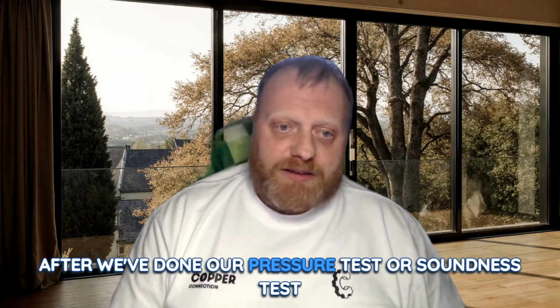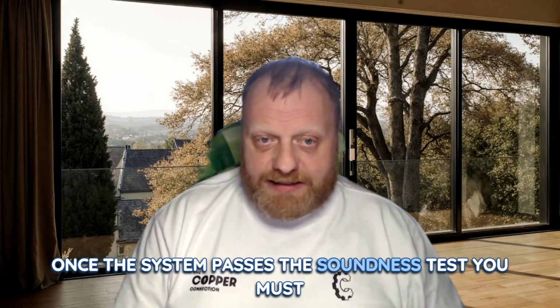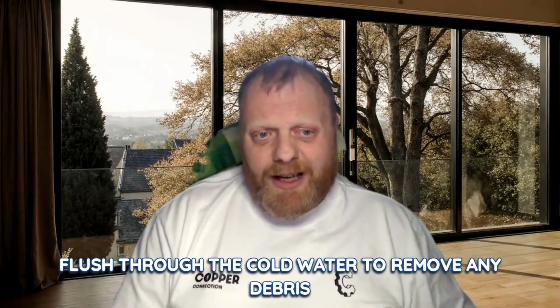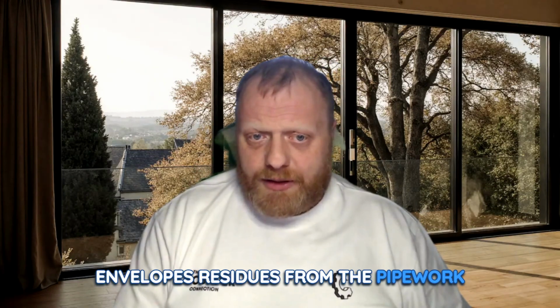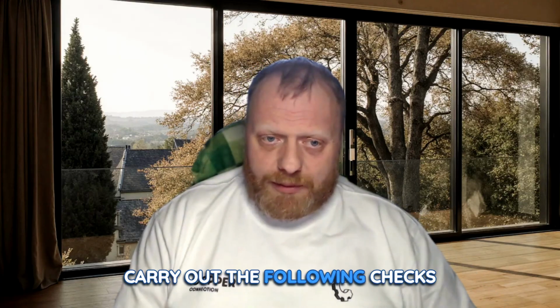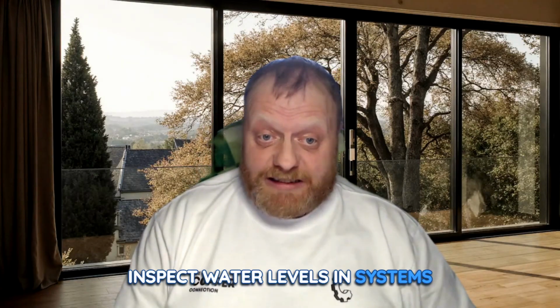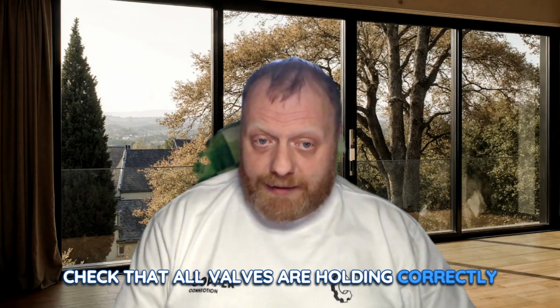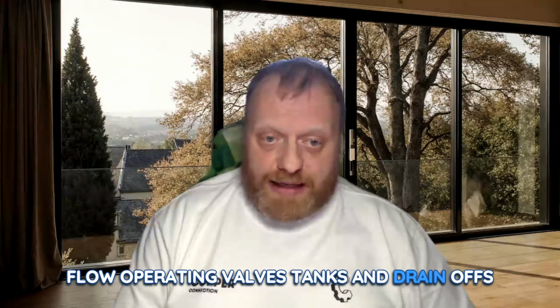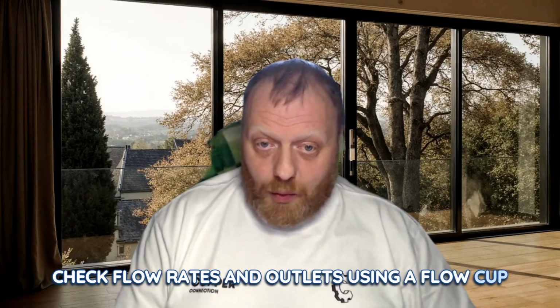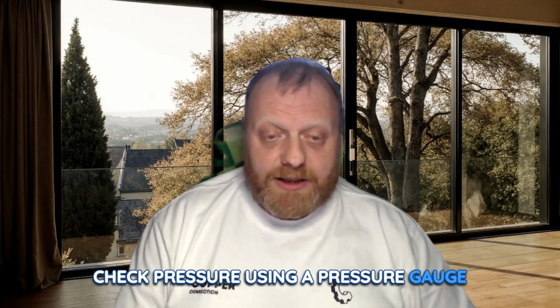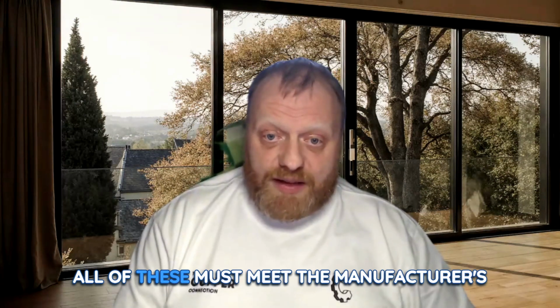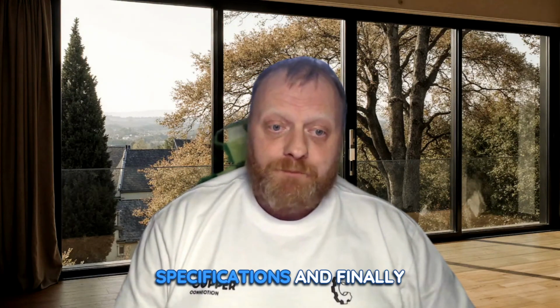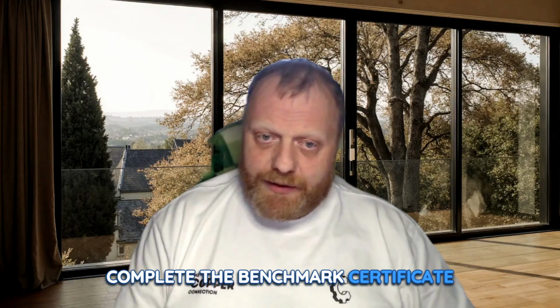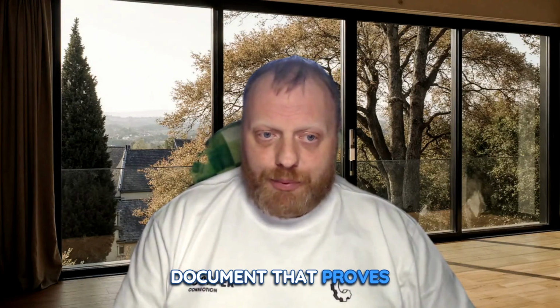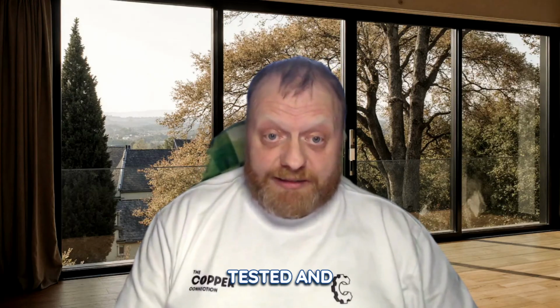So after we've done our pressure test or soundness test, once the system passes the soundness test, you must flush through with cold water to remove any debris and flux residues from the pipework. Then refill the system and carry out the following checks. Inspect water levels in systems. Check that all valves are holding correctly. Flow operated valves, taps and drain offs. Check flow rates and outlets using a flow cup or a weir cup. Check pressures using a pressure gauge. Check temperatures using a thermostat. All of these must meet the manufacturer's specifications. And finally, complete the benchmark certificate. This is an official commissioning document that proves the system has been installed and tested correctly.